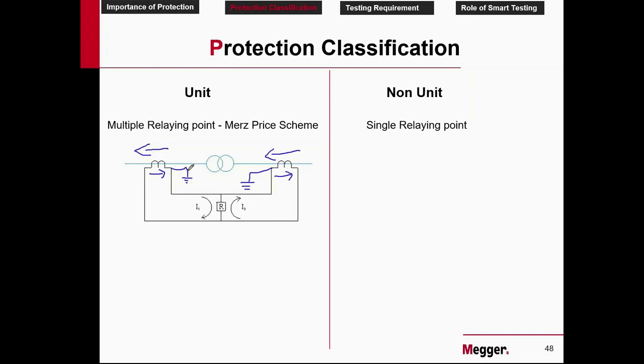So primary, earth to winding, secondary, winding to earth. Primary, winding to earth, secondary, earth to winding. And your CT star point will always be earthed towards the equipment that we are protecting. So this is the dot convention principle. According to this, you can follow this arrow mark. You will find that it flows like this. And you can follow this arrow mark. You can find that this is flowing like this.